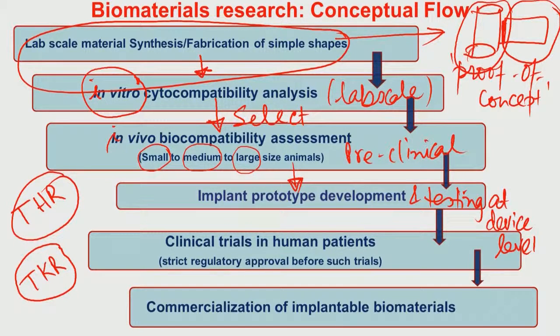So, once a large number of fatigue cycles are conducted using this hip simulator and the materials survive, the materials do not fracture, they do not wear to a significant extent, and their wear debris particles are taken and their non-toxicity at cell or tissue level has been established, then only all these preclinical test results are further transferred to the next level of study, that is called clinical trials.